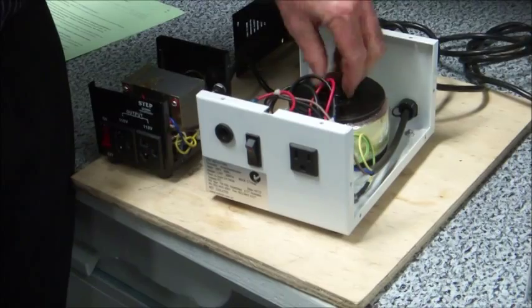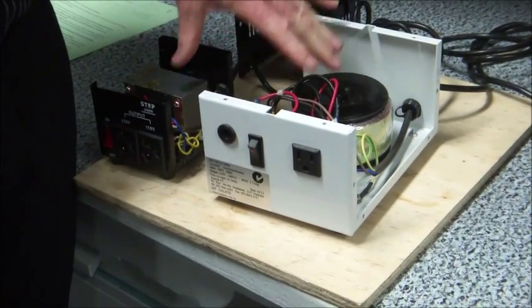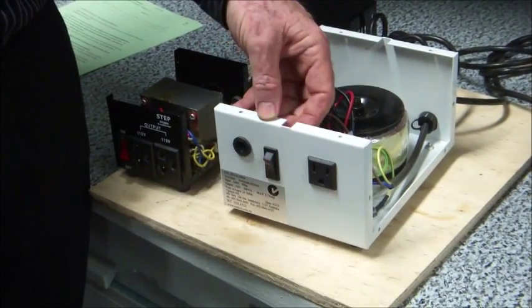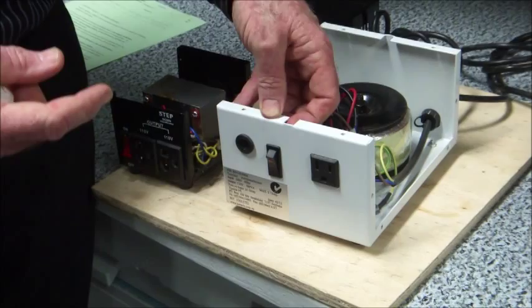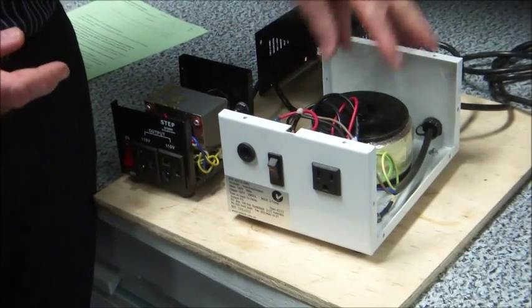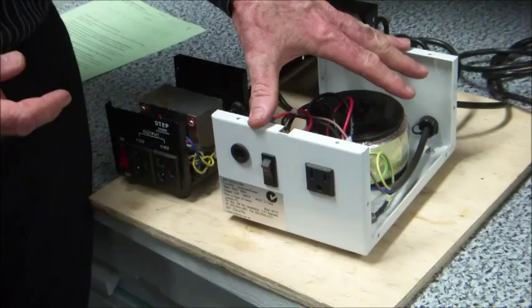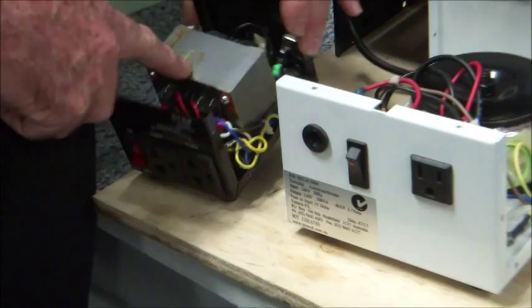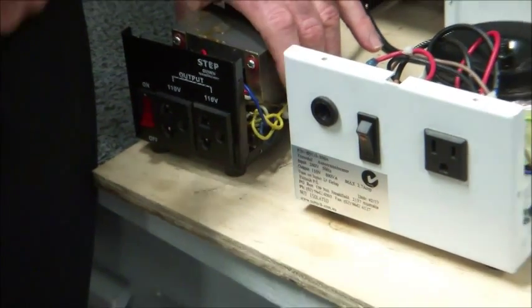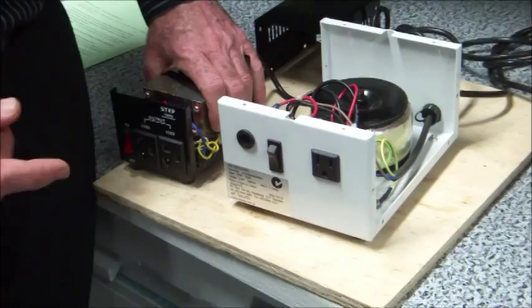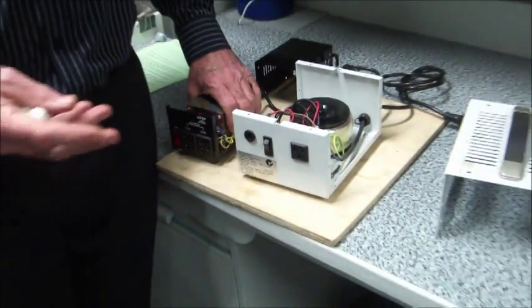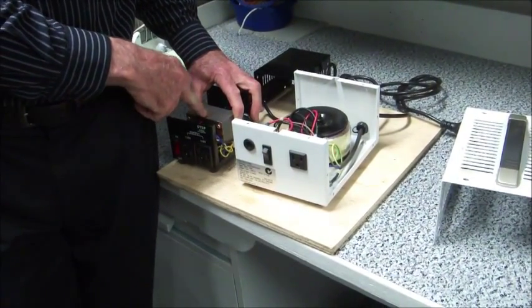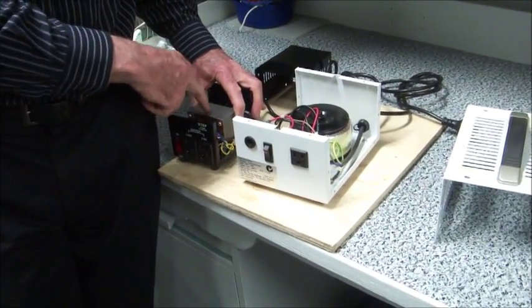I'm going to discuss now the ability of these transformers to deliver power to your device. If you have a device connected to these transformers and you want to run that device all the time, this transformer has the ability to give its full power 24 hours a day, seven days a week. This transformer is undersized. It will not be able to deliver the full power to your device, in other words, make your device run 24 hours a day, seven days a week. It's incapable. It is basically undersized.